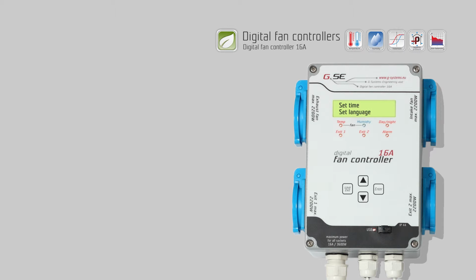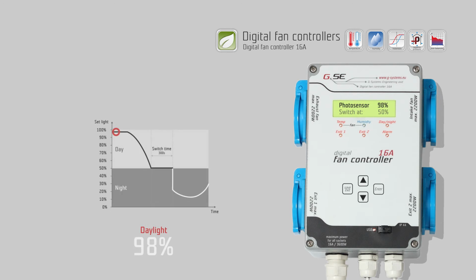Select Submenu Photo Sensor and press Enter. According to the day-night cycle, the controller selects the appropriate settings, which are previously set by you. The light sensor settings control the way day and night alternate. The first row shows the current measurement of the light sensor. Press Enter to set the level of alternation. If the value is set to 30% light, then the controller will switch settings when the light is below 30%.